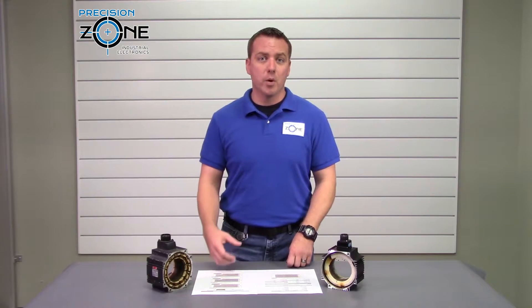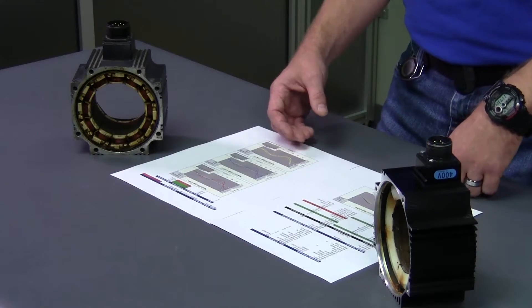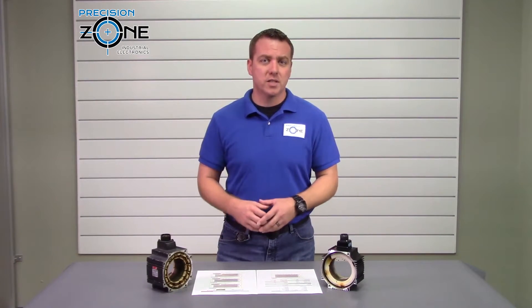Our Baker Motor Analyzer delivers reliable testing of stators with repeatable results. The Baker performs a wide range of electrical tests including surge, DC hipot, megohm, and winding resistance tests.